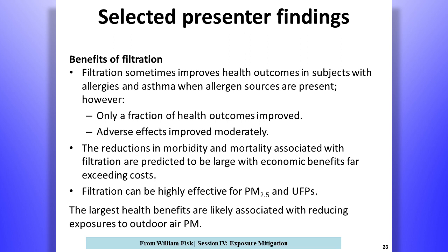He also talked about this growing trend to add nanofibers in the filtration industry. These nanofibers have diameters of less than 0.5 microns, as compared to, let's say, diameters of a few microns in the most common filters. And experiments in this area note that these nanofiber filters can produce a higher ratio of particle removal efficiency to air pressure drop. And there's, of course, also energy consumption related to the particle removal here as well.